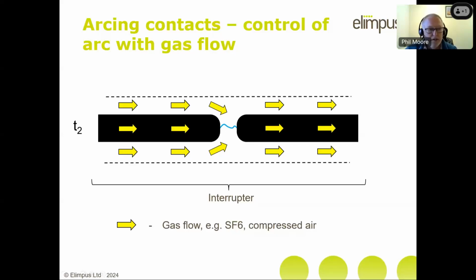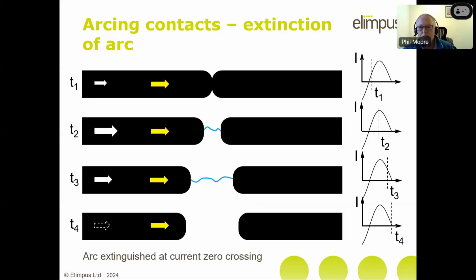there's a zero crossing. So I can just demonstrate the ideal state of affairs to get rid of an arc. You can see here on the right hand side, I'm showing you the current through the arc. This is represented by the white arrows. The yellow arrows are just to remind you that SF6 gas is being used to cool the arc down. So maybe at time T1, just a few milliseconds after the penultimate zero crossing, you begin to separate the contacts, and then at T2 we've got an arc going. As I said, you've pulled out this little thread, it's then developed into an arc.